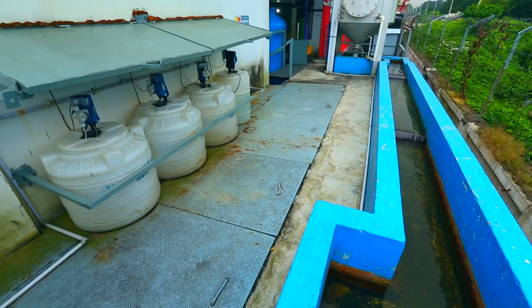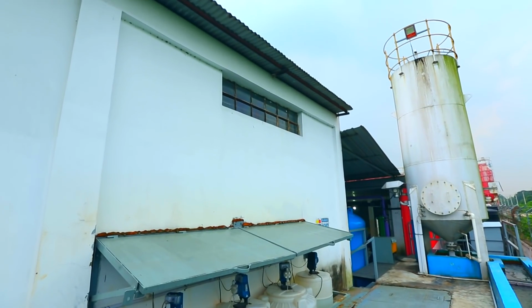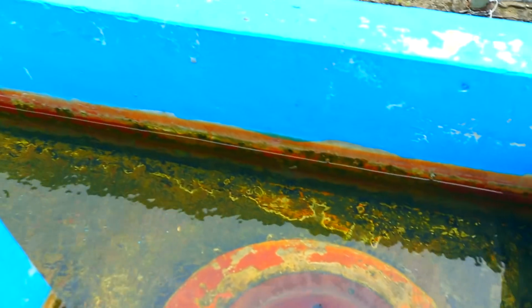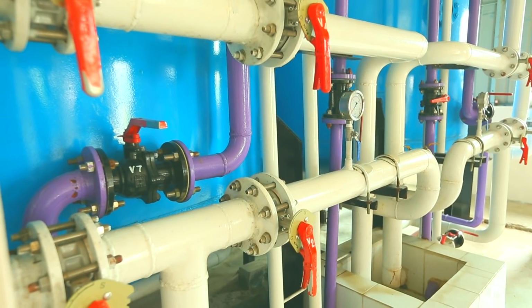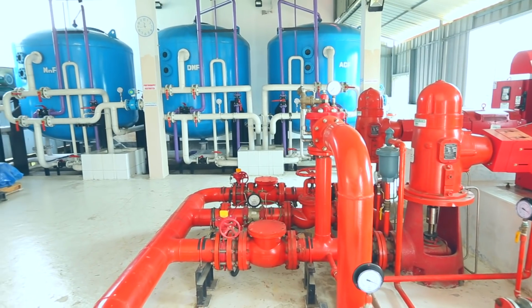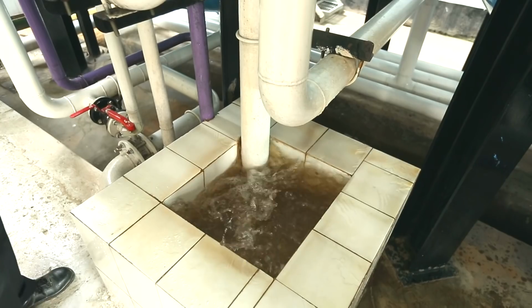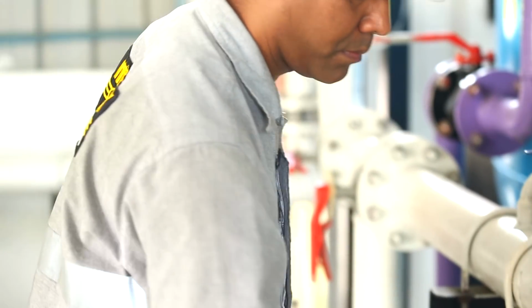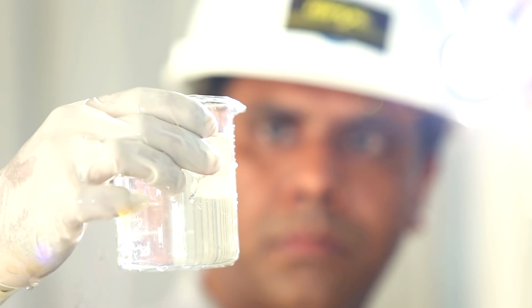In the pre-treatment process, water supplied by deep tube well is first passed through an aero-oxidation tower to oxidize and separate out the dissolved iron. The aerated water is then filtered through a series-connected manganese filter and dual media filter, followed by an activated carbon filter. The filter beds are cleaned by backwash regularly. The carbon-filtered water is then fed to RO membranes via micron filter.